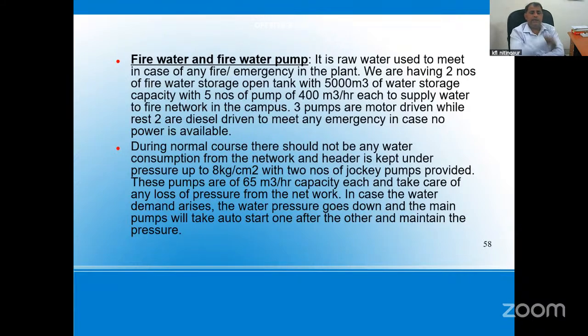When there is a reduction in the pressure, then one pump automatically starts and maintains the pressure up to 8 kg per cm square. If suddenly pressure goes down and reaches 6 kg per cm square, then all the pumps will start to maintain the header pressure.